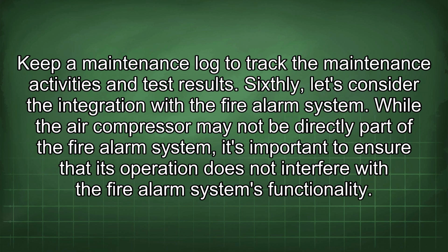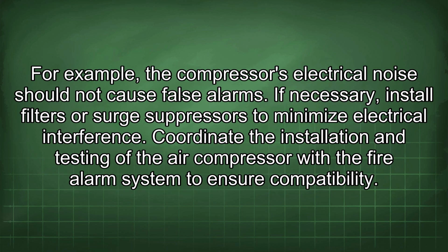Sixthly, let's consider the integration with the fire alarm system. While the air compressor may not be directly part of the fire alarm system, it's important to ensure that its operation does not interfere with the fire alarm system's functionality. For example, the compressor's electrical noise should not cause false alarms. If necessary, install filters or surge suppressors to minimize electrical interference. Coordinate the installation and testing of the air compressor with the fire alarm system to ensure compatibility.